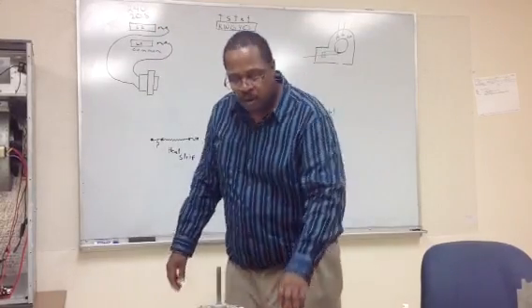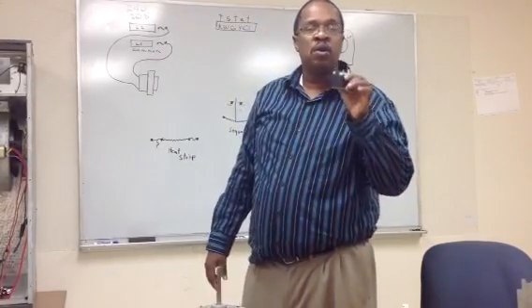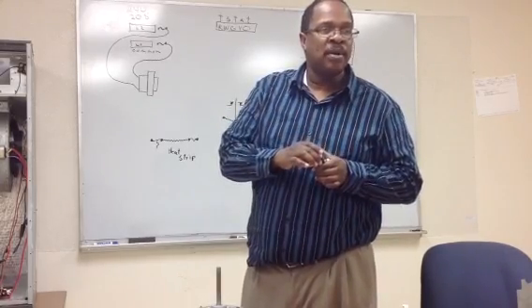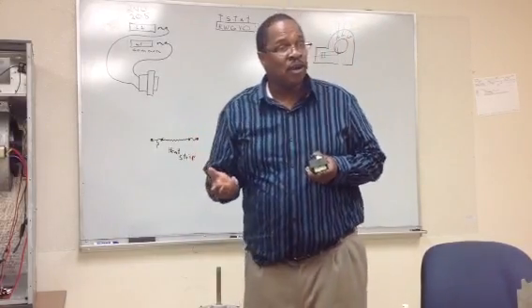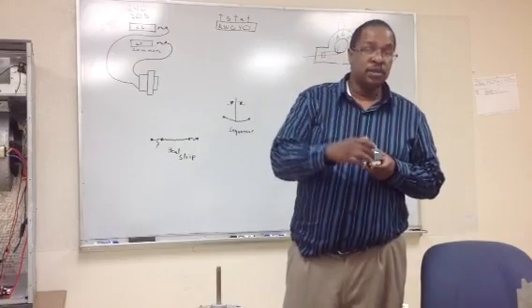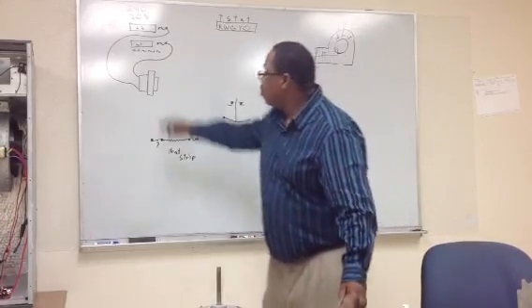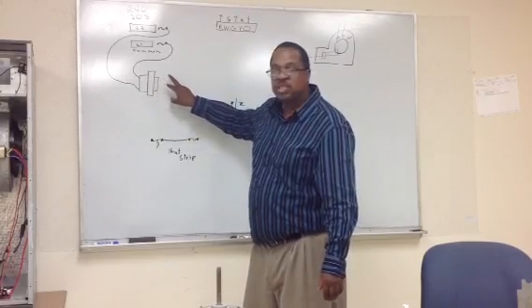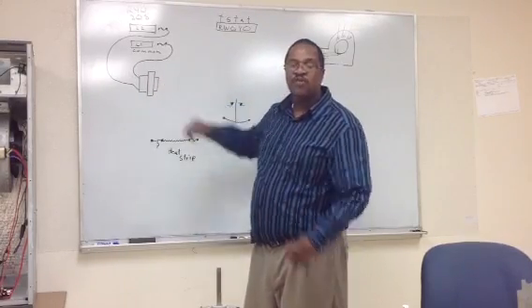In this building right here we use 208 voltage, not 240. So if I was wiring up this transformer, I will wire it up with 208. I will use common plus the 208 tap. If I was in a building and use 240, I will use common plus the 240 tap. Well anyway, we'll wire our transformer up, and now it will step down the voltage to feed our low voltage controls.